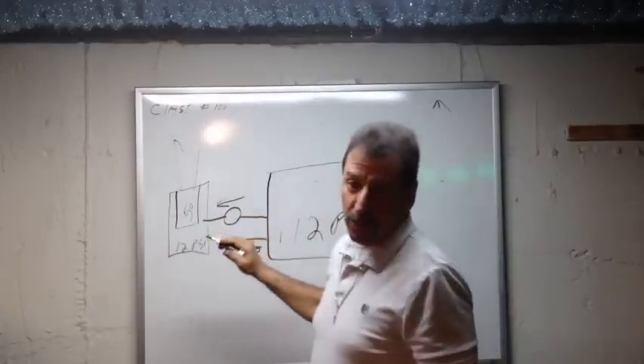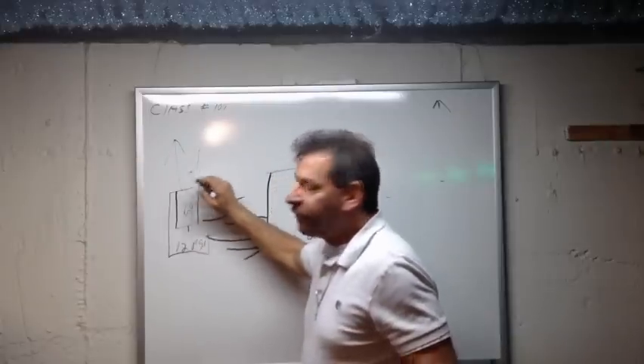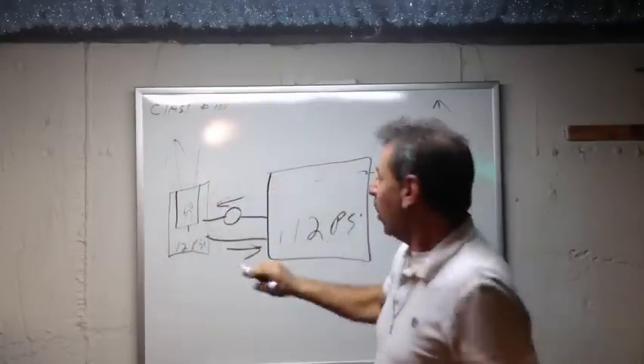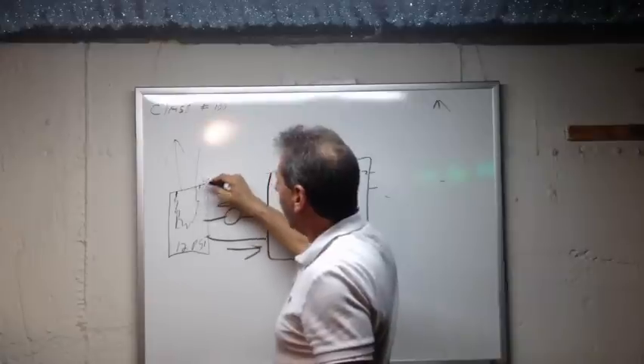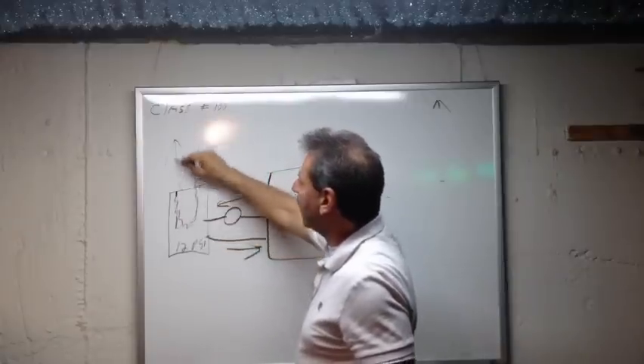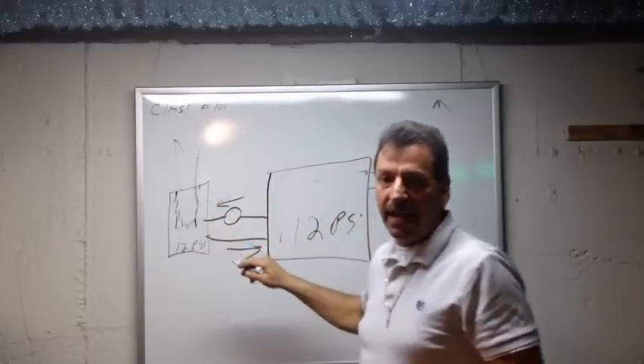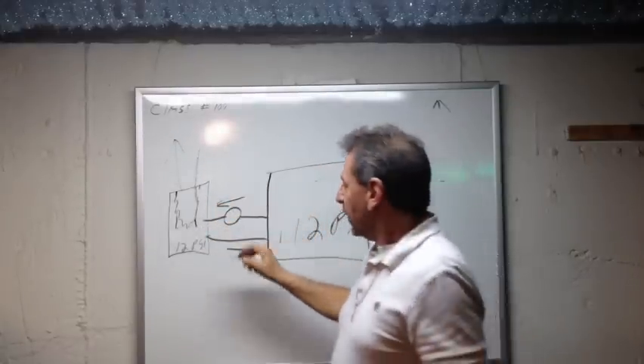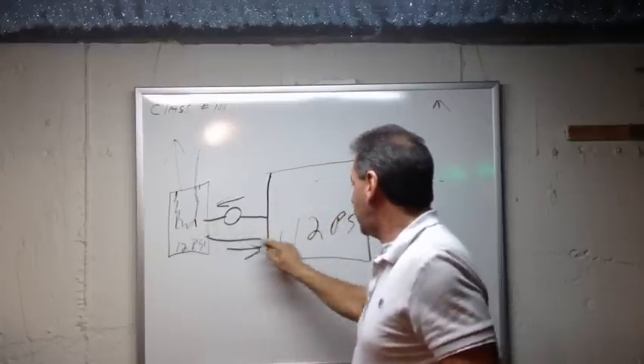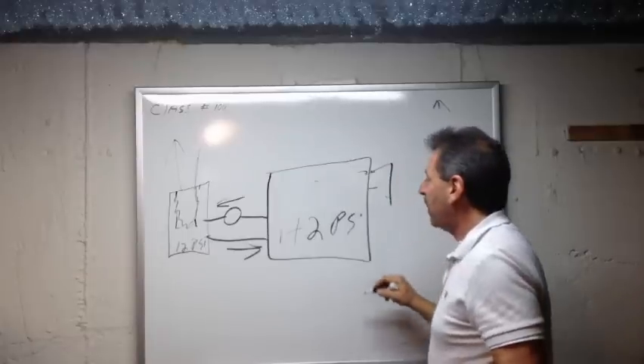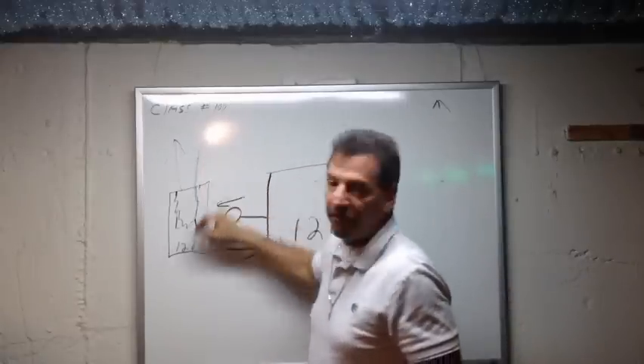Again, same scenario. 12 PSI of hot water from the boiler heating up the cold 50 PSI, making it warm so you can shower and use your house. Unfortunately, these tanks also fail where you can get a slight leak from the tank that's inside the tank. Or sometimes it could be a coil, depending on the design inside, where the cold water goes in and gets red hot and comes out hot. Once they spring a leak, now you have your 50 PSI, or your high-pressure water, leaking into your boiler water, which is all connected through the circulator and into the boiler, causing the relief valve to drip, because the 12 PSI will climb with that constant cold water feeding the tank.